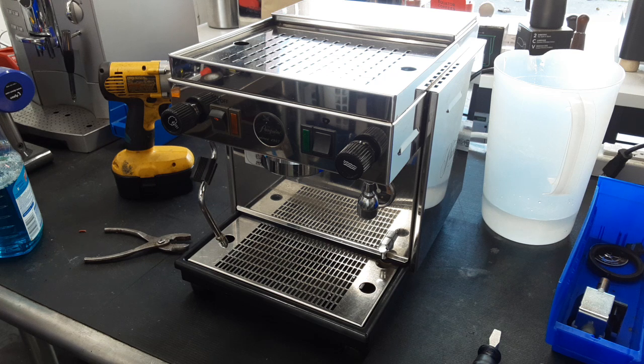It came in for quite a few issues, but mainly we had to replace the vacuum release valve, which was leaking a lot of pressure out through the top of the machine. We also replaced the water pump, which was from 2014, with a brand new one. We also did a tune-up, and had to take extra time descaling because there was quite a lot of scale in there.